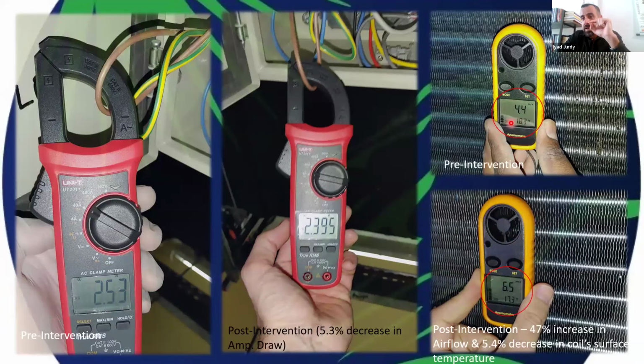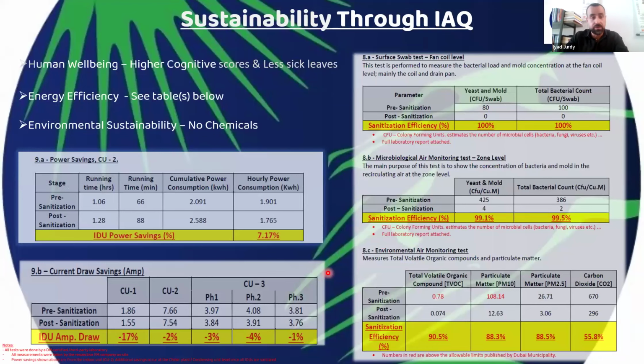What you notice here is that this surface temperature was 18.3 Celsius, and it dropped down to 17.3 post-sanitization and cleaning. So you're going to notice not only energy efficiency at the fan coil level, but also energy efficiency and power saving at the chiller level, or the condensing unit level, with all the indoor units connected to it. It all adds up because you see an amazing decrease in the surface temperature of the coil.